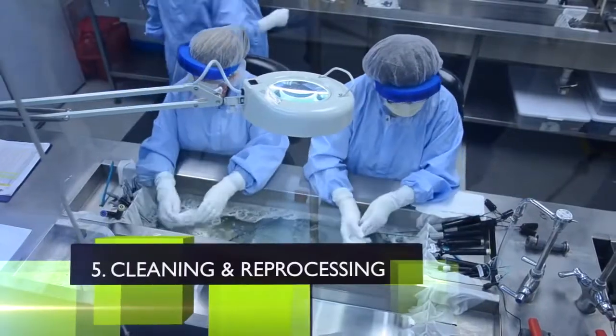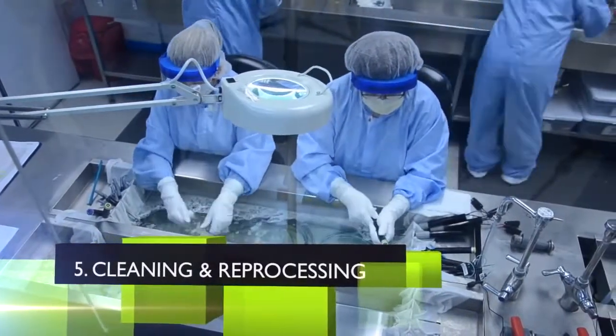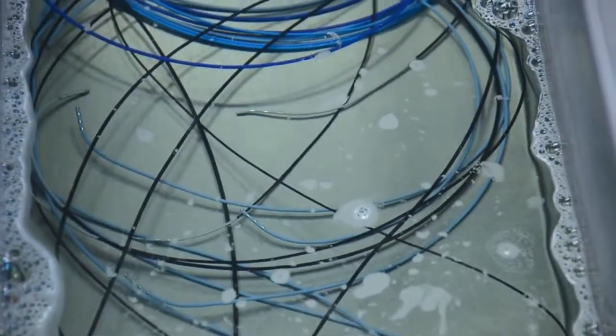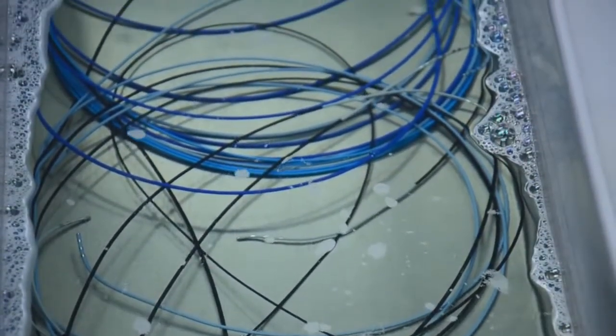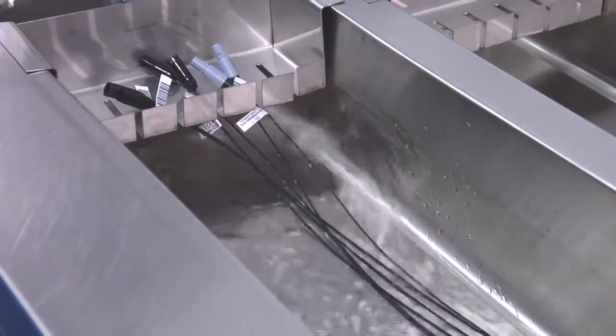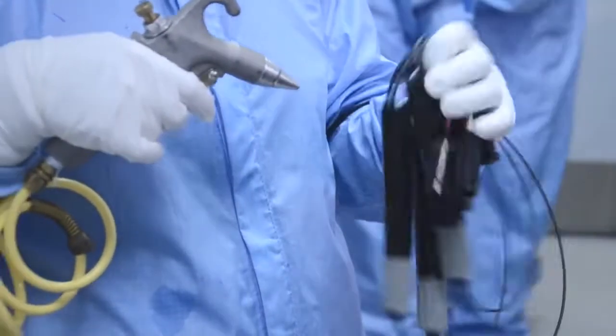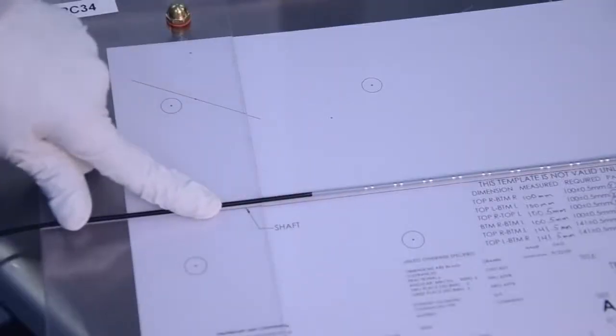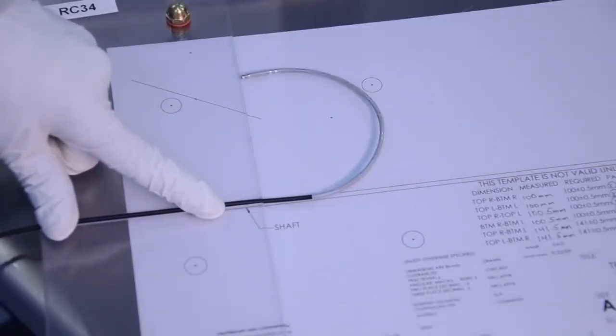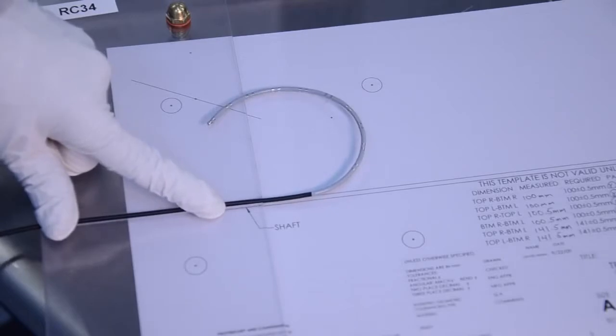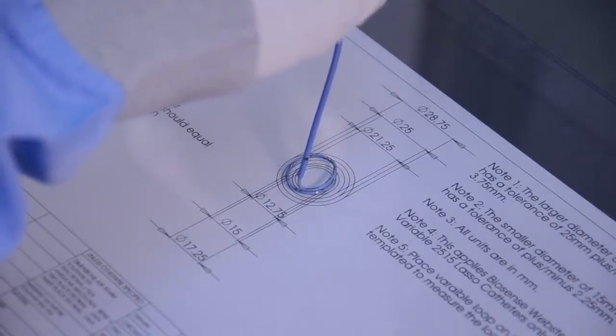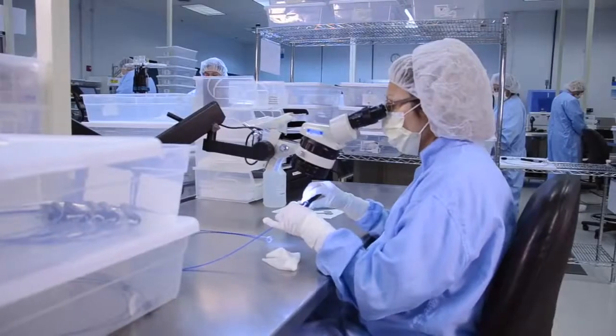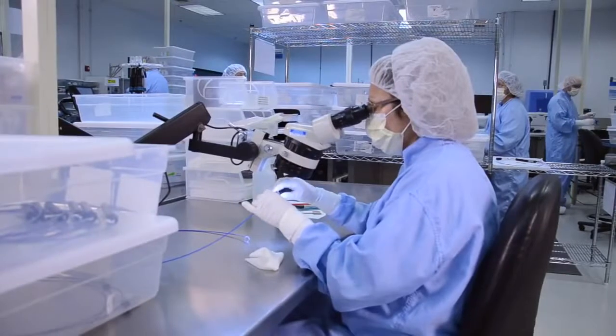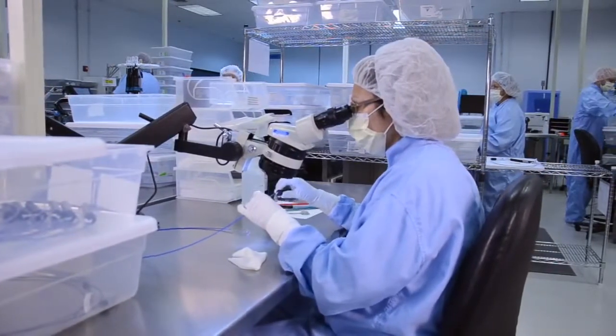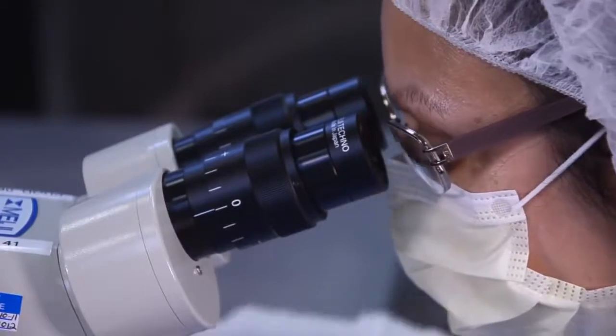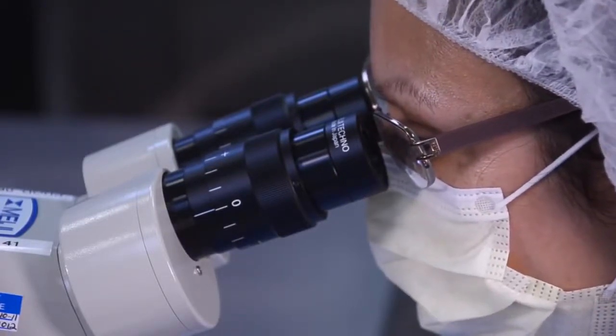Once inspection is complete and the device has been properly identified, EP catheters undergo cleaning using a pH-neutral enzymatic solution and suitable cleaning agents. The catheters are then thoroughly rinsed to remove all cleaning chemicals and dried in preparation for performance testing. Dried, clean catheters are then checked for curve performance on templates. Any catheter that does not meet stringent curve specifications is rejected. Next, the catheters are inspected under magnification for kinks, damaged handles, tags, abrasion, and contamination. Following proper collection protocol for all catheters is critical for minimizing curve failures and for yielding maximum savings.